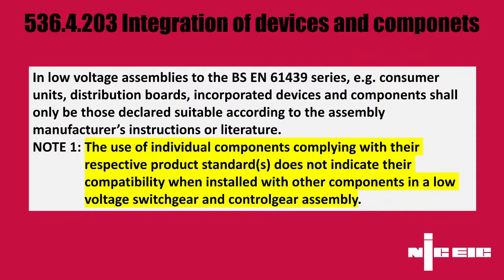So yes, unless you want to take responsibility, which we would suggest is not typical because it's very onerous, then you really need to rely on those manufacturer's instructions. And they're not doing it as a get out, they're really doing it to confirm that they are the designer of that assembly, and they will guarantee its characteristics, providing you stick with their instructions. So that's where that comes about from.